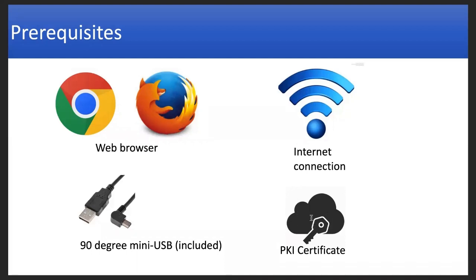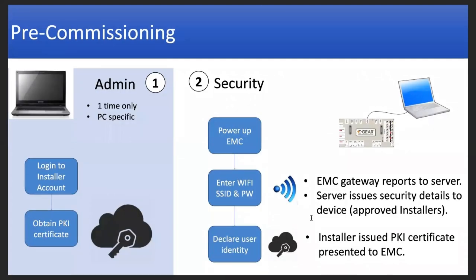The PKI certificate, again, is a security certificate that you will issue from your installer admin account to your installer field laptops, to those devices. Those are pre-commissioning steps, one time only, and specific to each laptop. Sort of an administrative step here. You would log in and you would get that PKI certificate. Those PKI certificates are good for a year, so you've got to do it once every year. Once the system is turned on, the EMC connects to the cloud. That cloud connection will then download the list of PKI certificates, or approved installers, that are allowed to access it and do the commissioning.